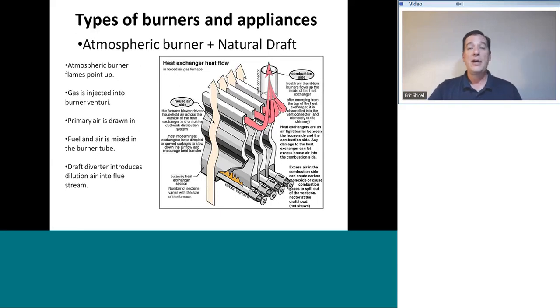As I said before, it's a very common thought that the heat of combustion causes flue products to rise up. And to a minor extent, that does actually happen. What adds to this misconception is the fact that the temperature difference between the inside and the outside also strengthens the draft. You will have a stronger draft on a very cold day than you do on a warm day. Good to know about water heaters. As the vent warms up, the draft gets stronger.